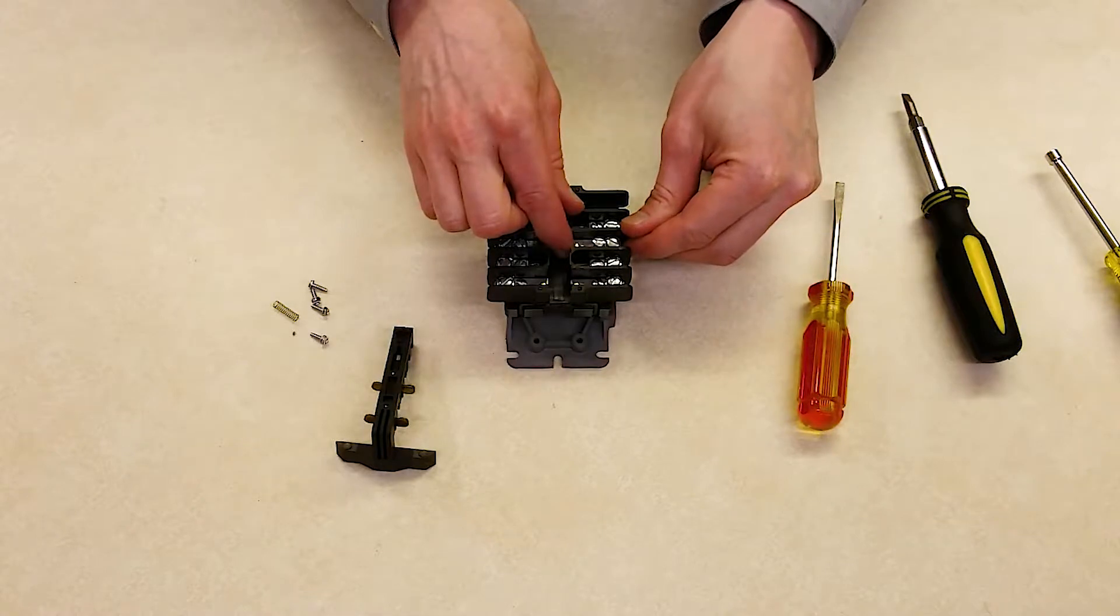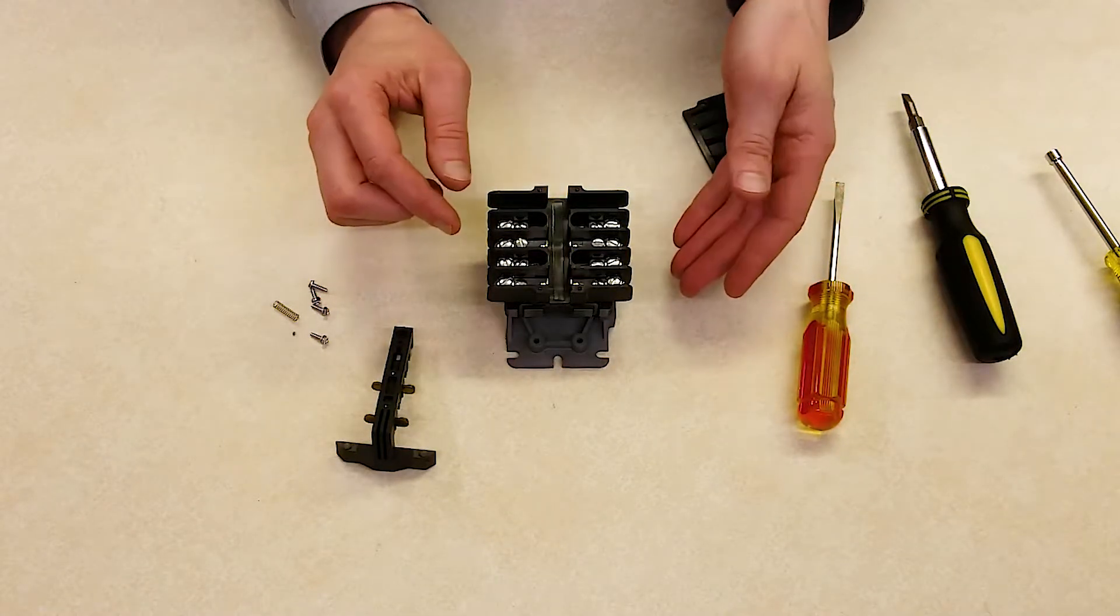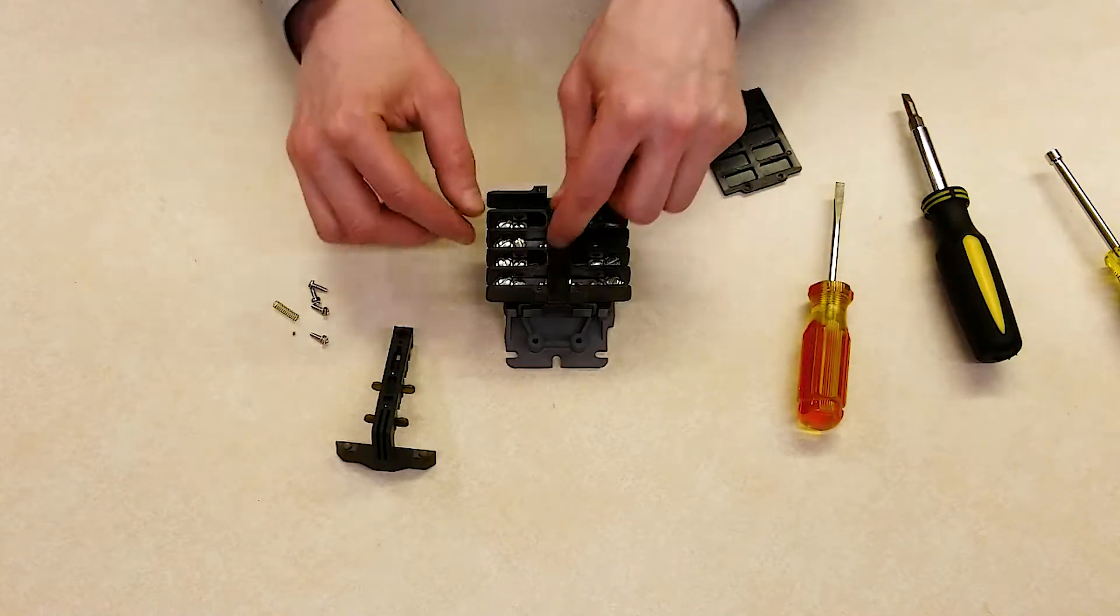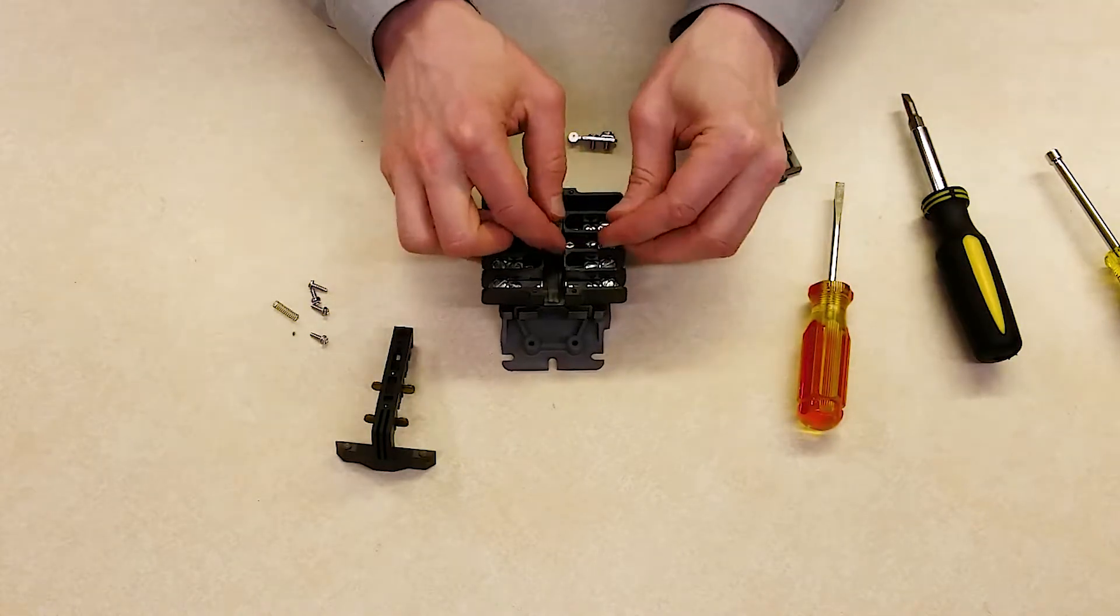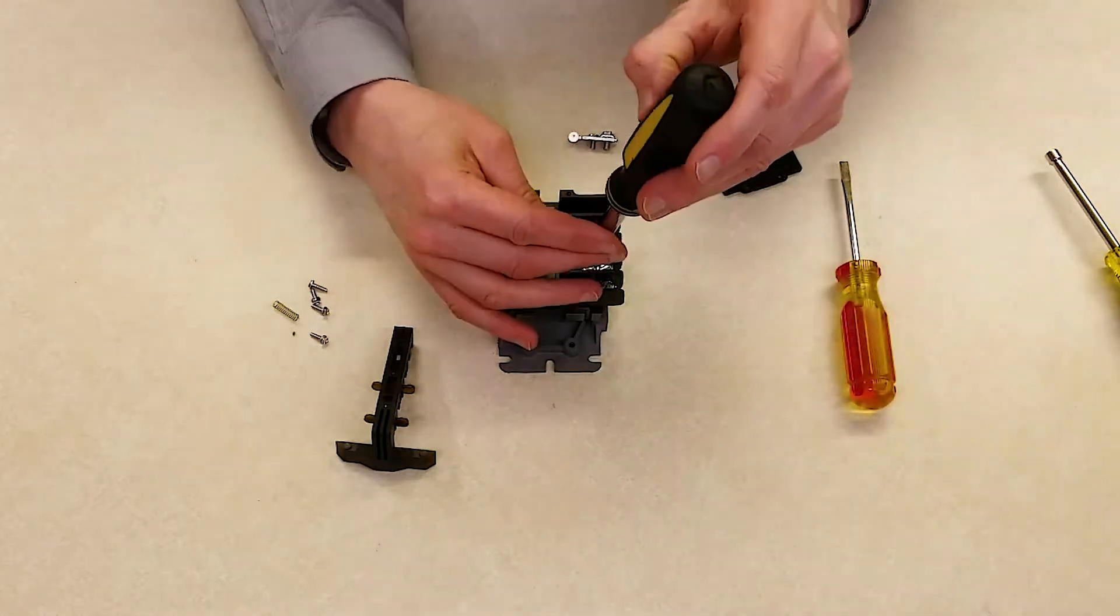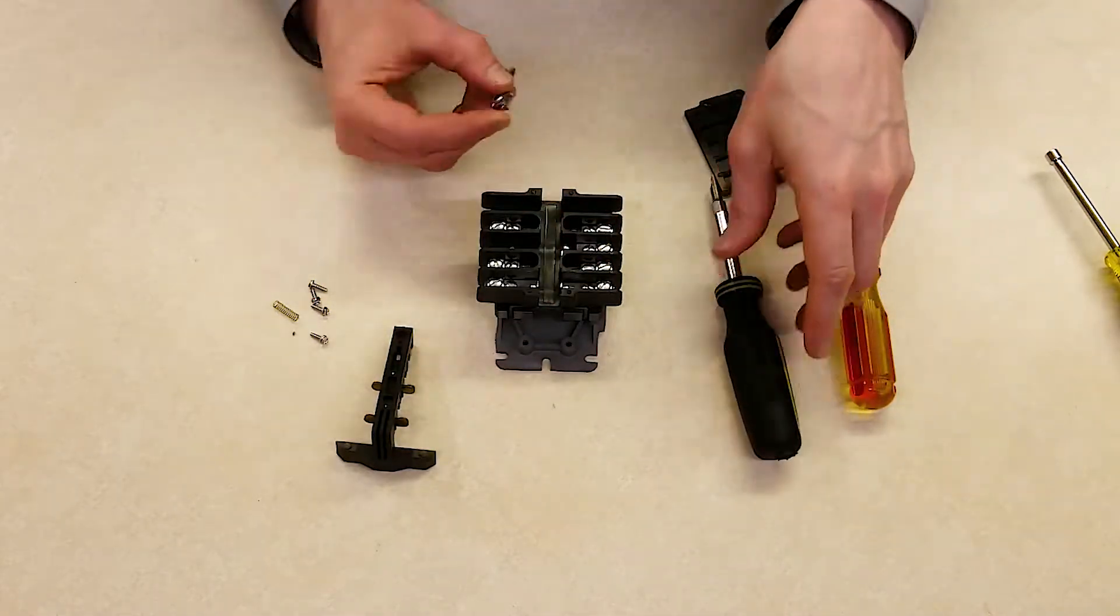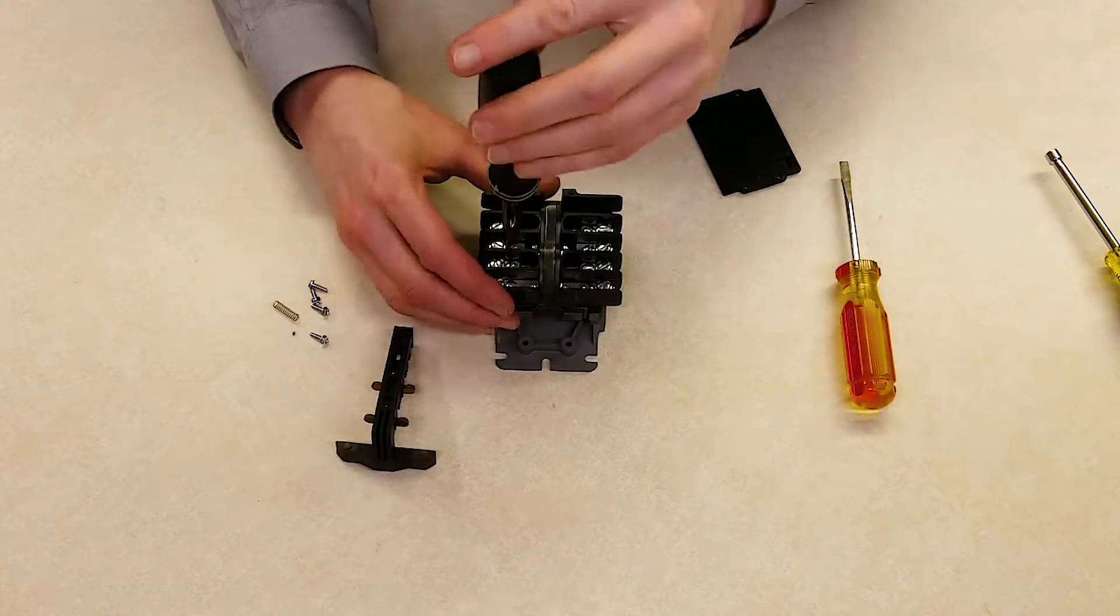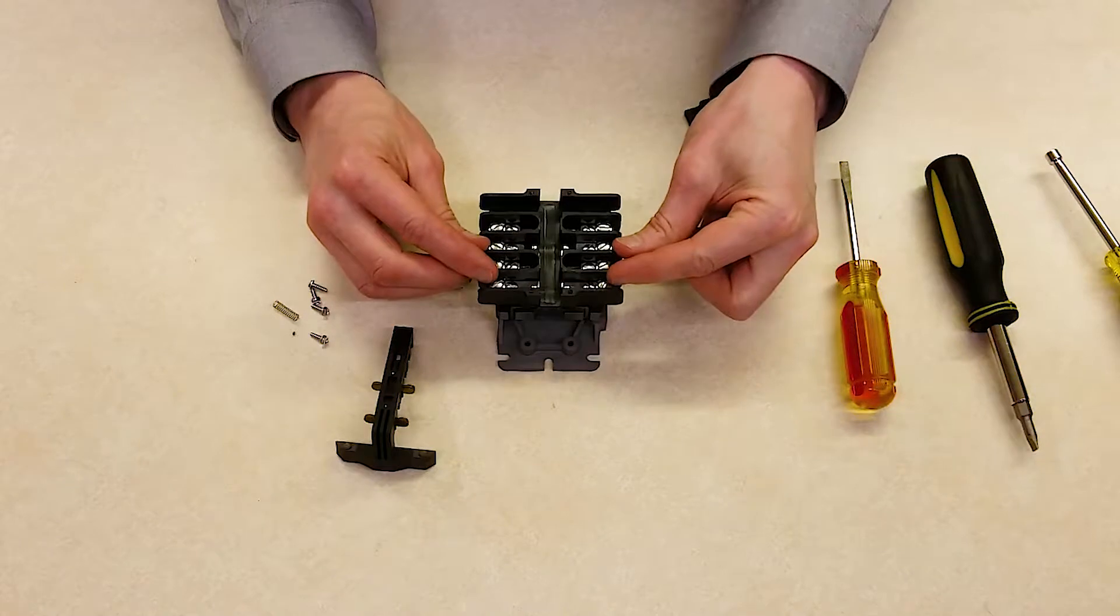Now I could replace these with a new contact kit. In this case, all I want to do is change it to normally closed. So I'm going to remove each side and swap them. You can see now that the contacts are facing in opposite directions.